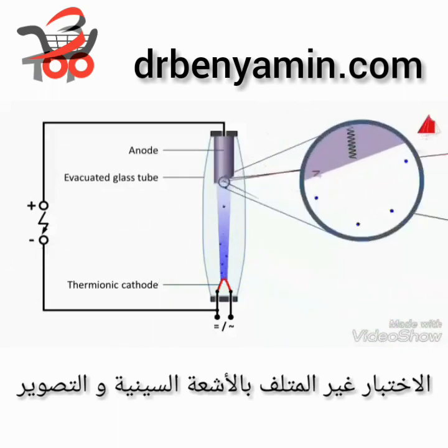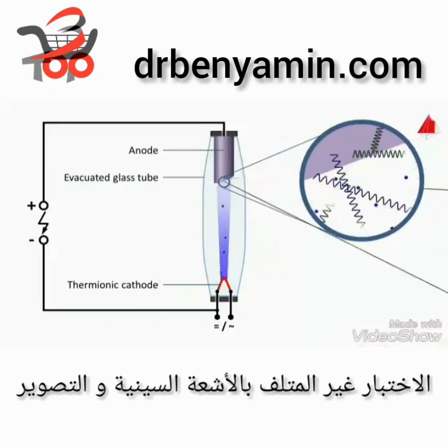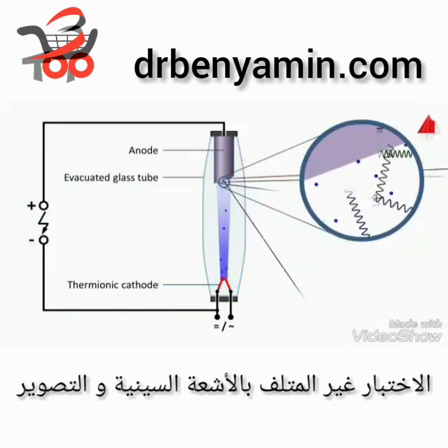The electron beam collides with the anode at high velocity. The anode material slows down the electrons within a very short distance. This generates the desired X radiation, but unfortunately also a lot of heat, which has to be dissipated by cooling.